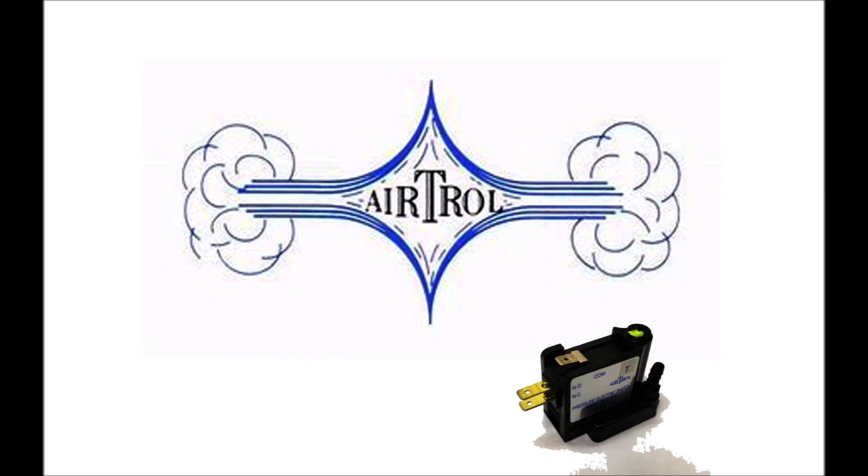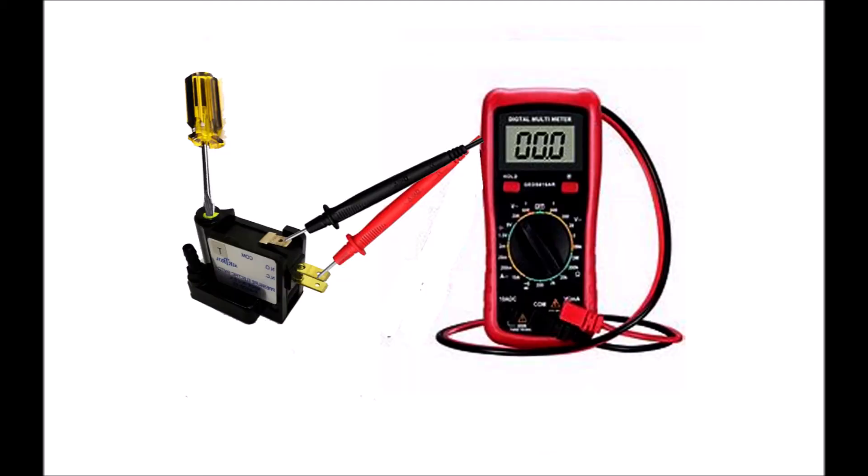To check for continuity on the new switches, I connected them to an ohmmeter and turned the screw in until the normally open contact should have made contact. I tried in and out, screwing them, nothing worked. Then you're supposed to back it off half a turn or so after making contact.